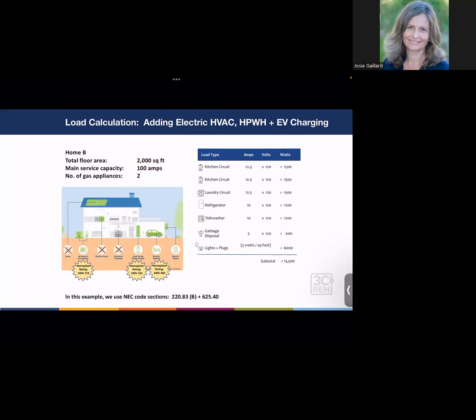Same home, actually, sorry, different home, 2,000 square foot home this time. Similarly, 100 amp panel, so still a relatively quote unquote small panel. This time we're going to convert not just one appliance, we're going to convert 3 appliances and see how the math looks. So all the existing appliances on the right are all the same. The 2 kitchen circuits, 1 laundry circuit, refrigerator, dishwasher, disposal. Light and plug loads is different here because it's 3 watts times 2,000 square feet instead of 1,500 square feet in the last example.